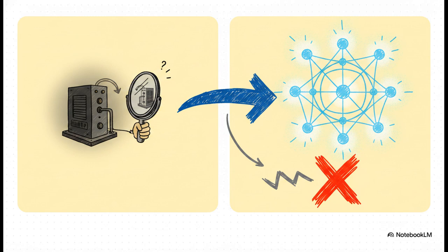Let's look at how that manufacturer data transforms when we run it through the formula. So, that generator nameplate says 15% reactance on a 15 MVA base, right? But when we mathematically adjust it to fit our 100 MVA system study, we see the normalized data become 100% reactance on that new base. It's a completely different value. Translating the equipment's worldview into your system's worldview is literally the only way to ensure your network simulations actually reflect reality.